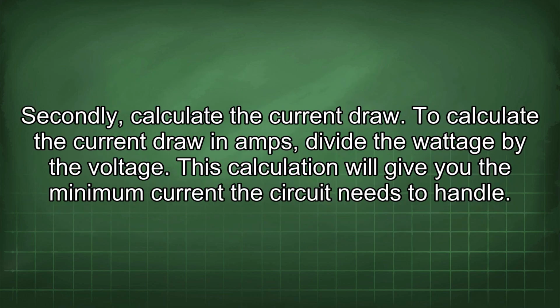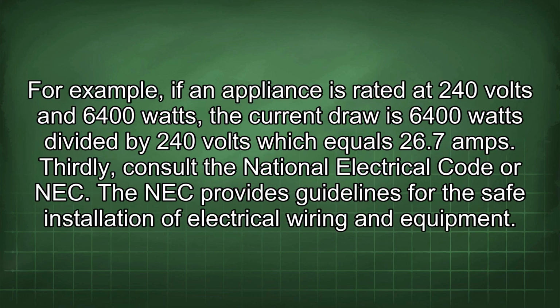Secondly, calculate the current draw. To calculate the current draw in amps, divide the wattage by the voltage. This calculation will give you the minimum current the circuit needs to handle. For example, if an appliance is rated at 240 volts and 6,400 watts, the current draw is 6,400 watts divided by 240 volts, which equals 26.7 amps.